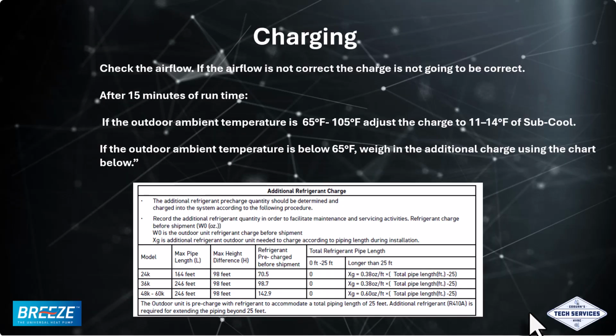When charging the unit, check the airflow. If the airflow is not correct, the charge is not going to be correct. We want to turn our unit on for a minimum of 15 minutes. If the outdoor ambient temperature is between 65 and 105 degrees Fahrenheit, we'll adjust the charge to 11 to 14 degrees of subcool.